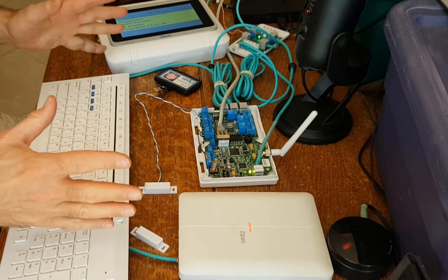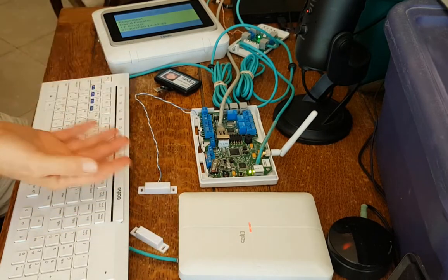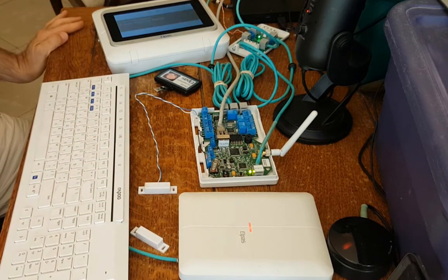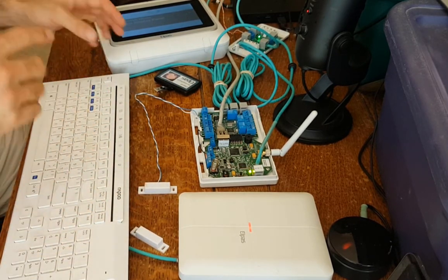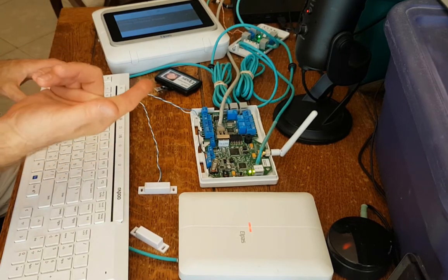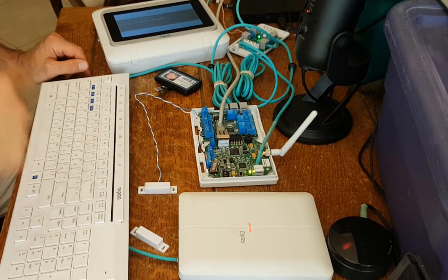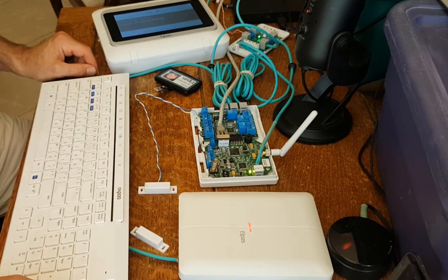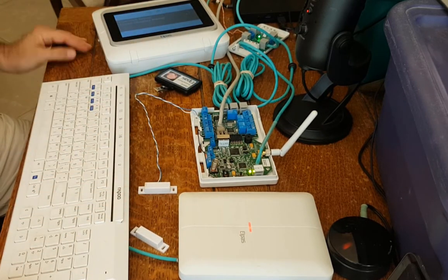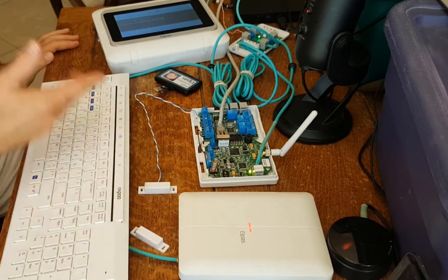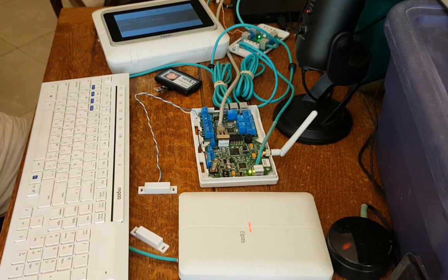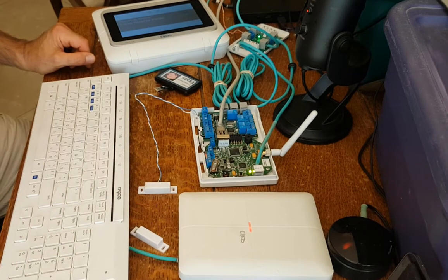Now, of course, instead of setting the beep, you can set a command to lock the door. Instead of using the door contact condition, you can use, or in addition to, a button press on a nurse call badge or a pin code on a keypad; see my other video on that. That's the basic functionality. You can set rules again for a tamper. That's button 2 on your tag. So if you have a patient wandering system, you can also alarm for the tamper if they cut open their band. And it could be used as a general panic alarm.